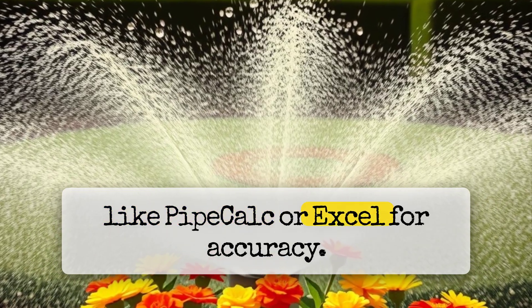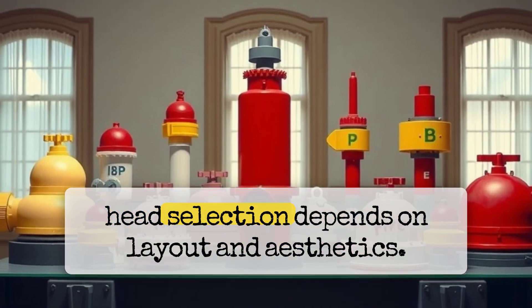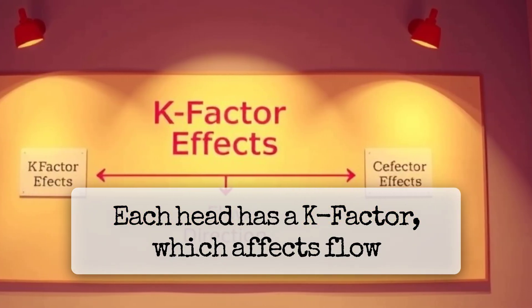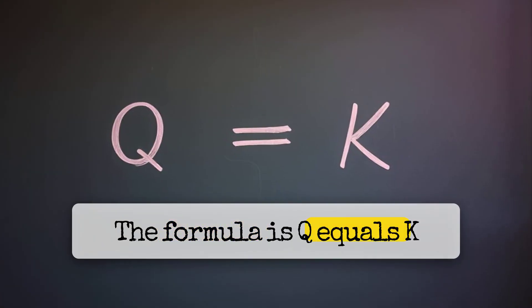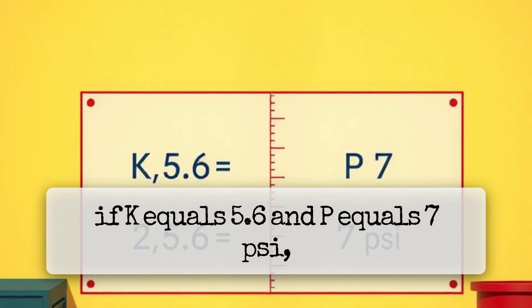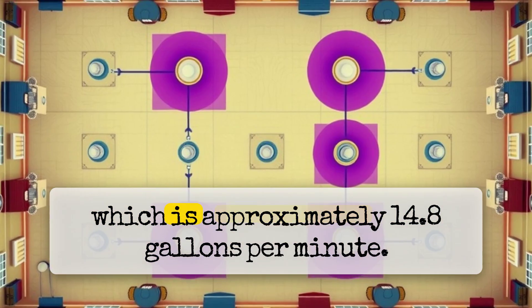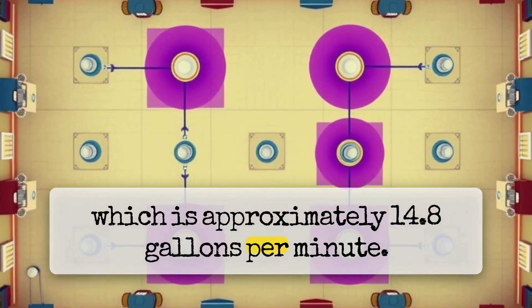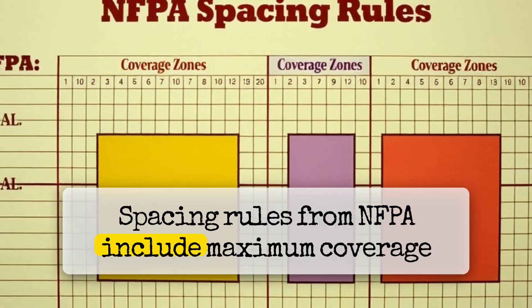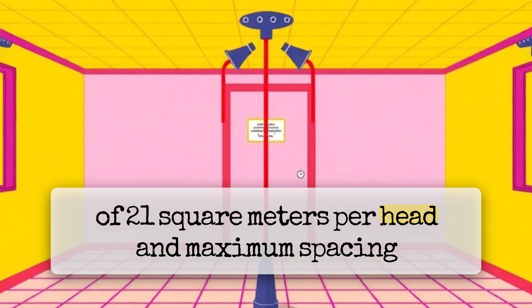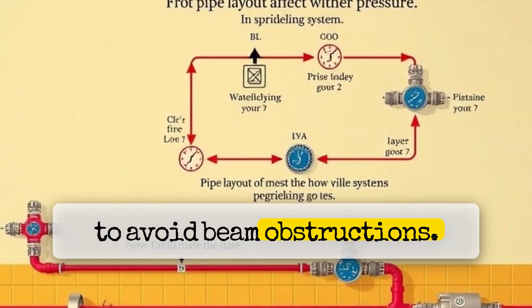Use software like PipeCalc or Excel for accuracy. Sprinkler head selection depends on layout and aesthetics. Each head has a K-factor which affects flow rate. The formula is Q equals K times the square root of P. For example, if K equals 5.6 and P equals 7 PSI, then Q equals 5.6 times the square root of 7, which is approximately 14.8 gallons per minute. Spacing rules from NFPA include maximum coverage of 21 square meters per head and maximum spacing of 4.6 meters. Heads must be aligned to avoid beam obstructions. Choose temperature rating and coverage wisely.